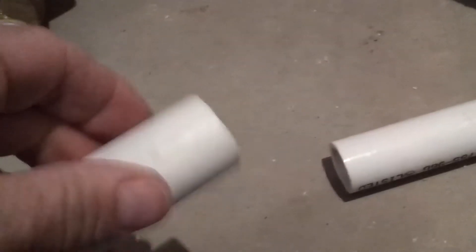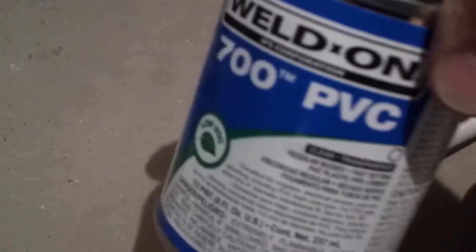Your valve may be different, so make sure you're following the instructions of the RPZ valve. We've got PVC here so we've got to glue it together to assemble it. Make sure you use appropriate PVC primer and glue. We're using OD purple primer and Weld-On 700 PVC glue — it doesn't have to be the same company.